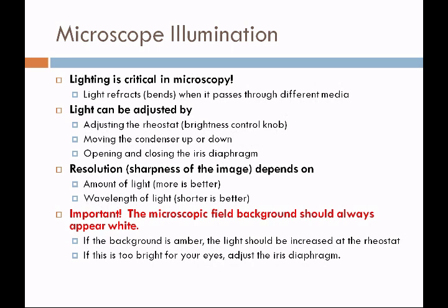It's very important that the microscopic field, when you are looking through the microscope, is white. If it appears amber colored, you don't have enough light and you will not get the best resolution. If you find that you have white light in the background but it's too bright for your eyes, adjust the light at the iris diaphragm instead of at the rheostat.